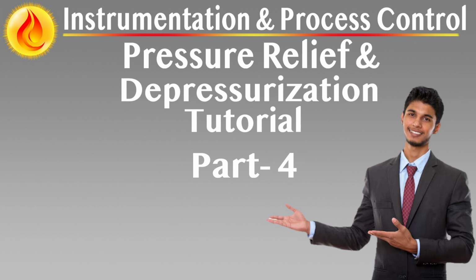Back pressure considerations. Sizing starts from the flare or vent tip, where the outlet pressure is atmospheric or choked, and works backward toward each relief or depressuring source. Pressure drops through each section are calculated cumulatively to determine the built-up back pressure at each valve outlet.